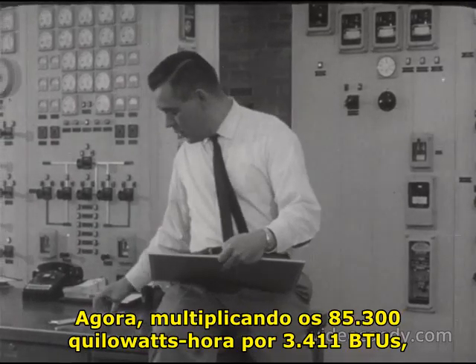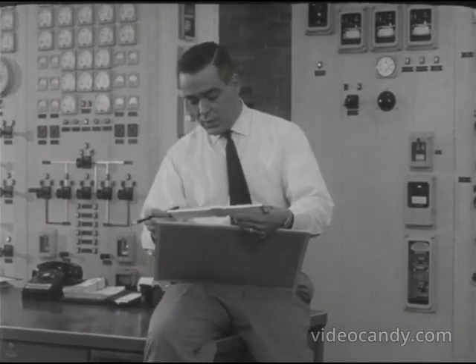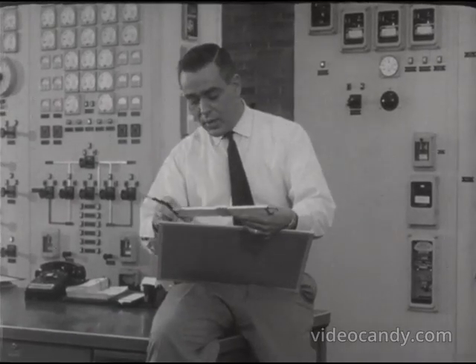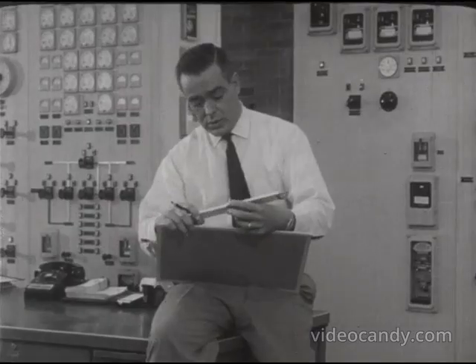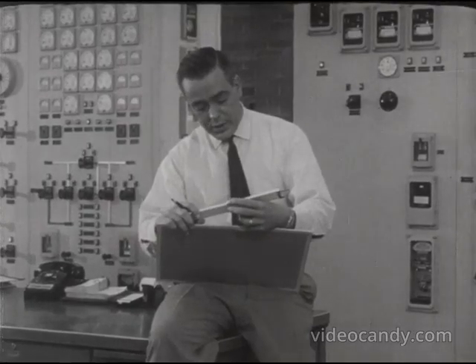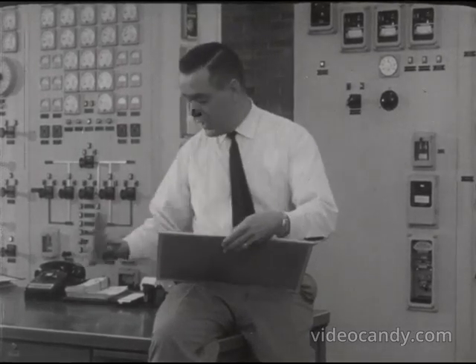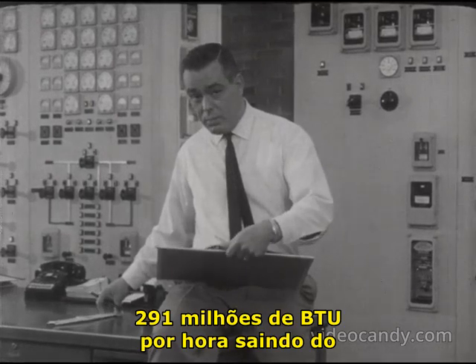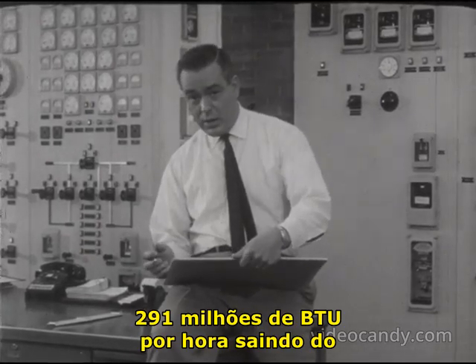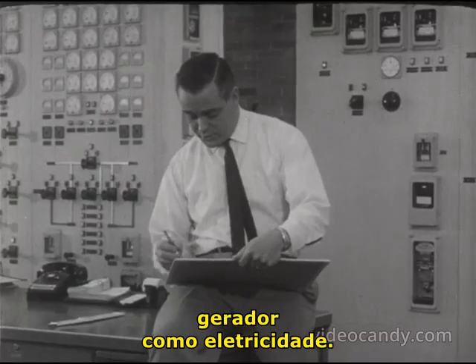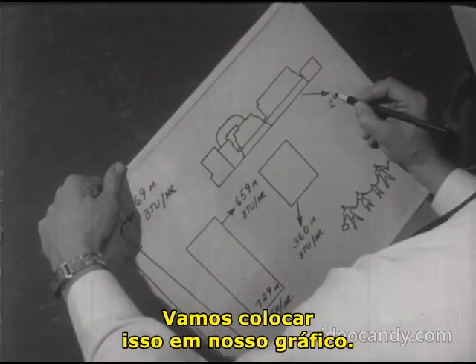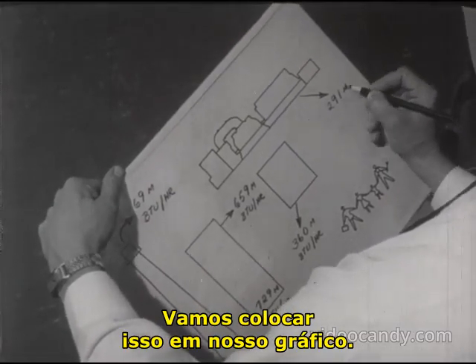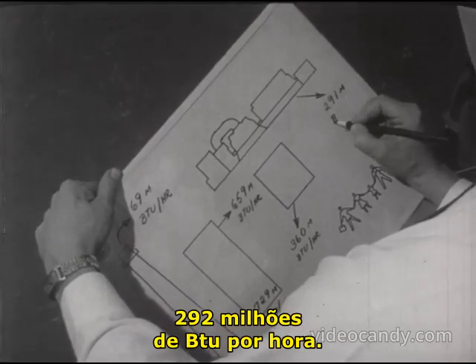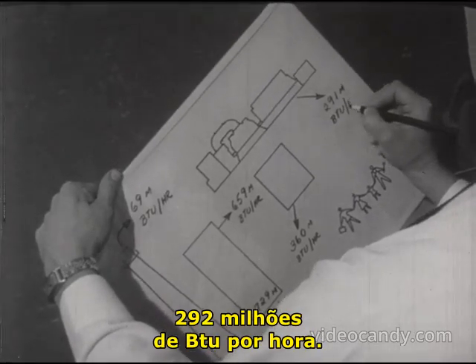Now, multiplying the 85,300 kilowatt hours by 3,413 BTU, we find that we have 291 million BTU per hour coming out of the generator as electricity. Let's put that on our chart. 291 million BTU per hour.